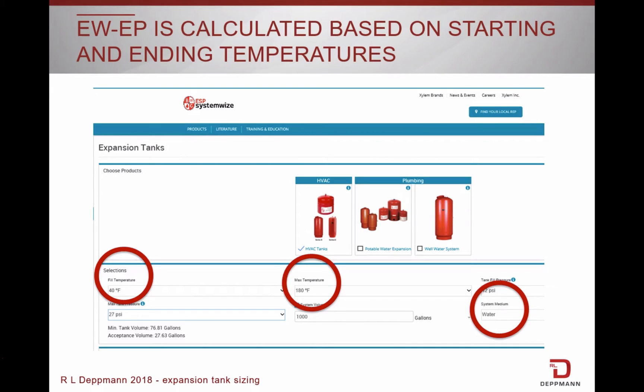Here is the screen from the Bell & Gossett ESP System-Wise Selection Program. As you can see, on the left is the system fill temperature, in the middle is the maximum temperature, and on the right is the liquid we are using. Expansion of the water (EW) minus the expansion of the pipe (EP) is calculated based on the fill temperature, maximum temperatures, and the liquid.